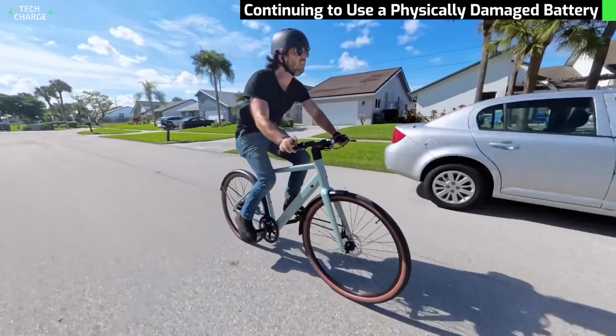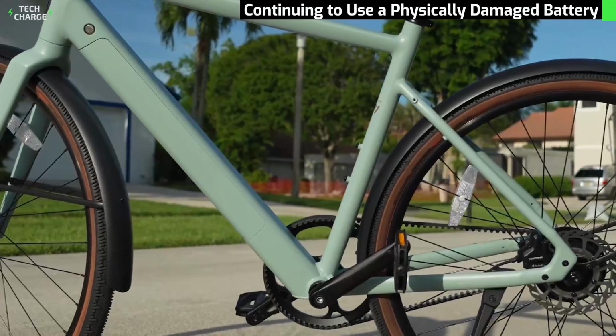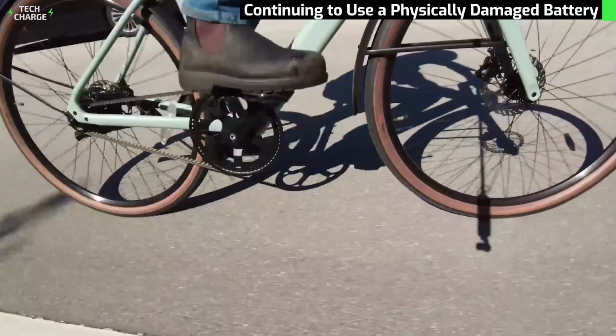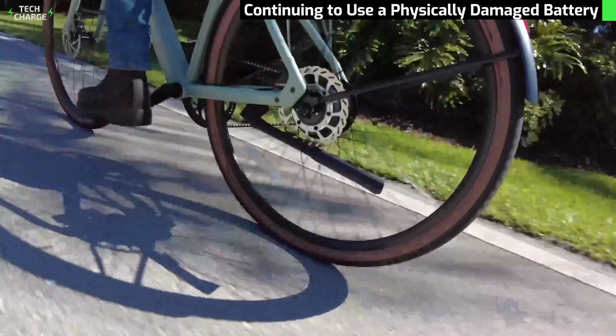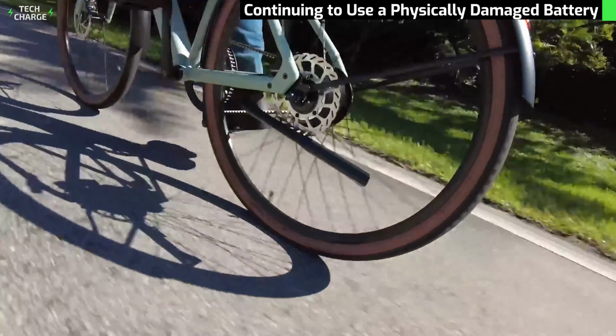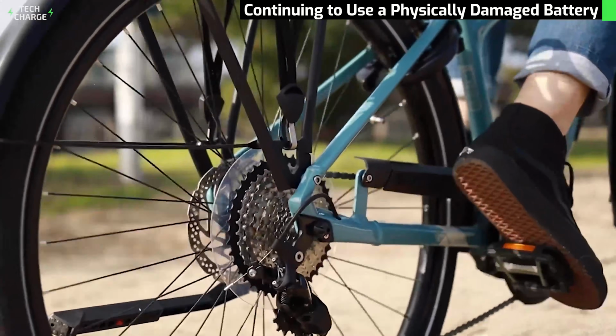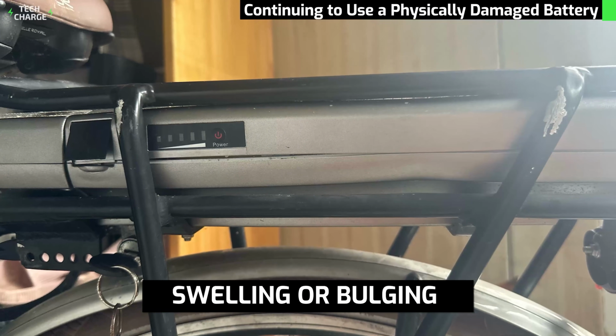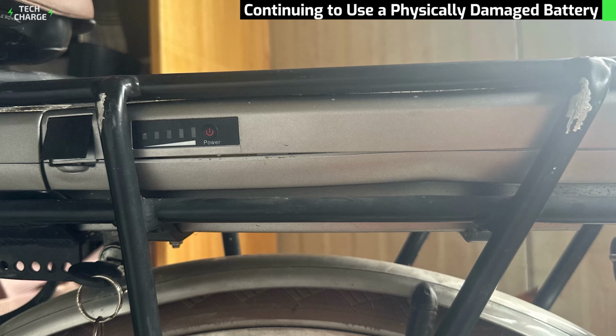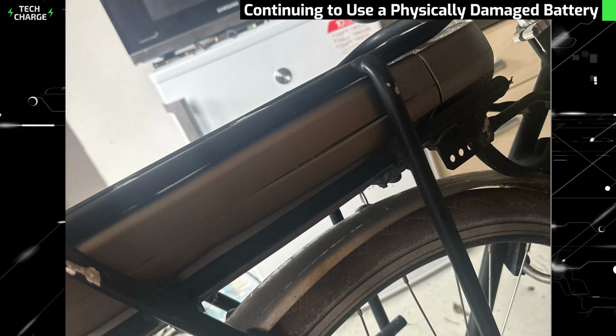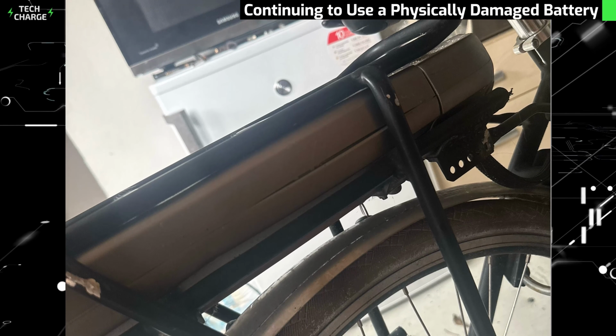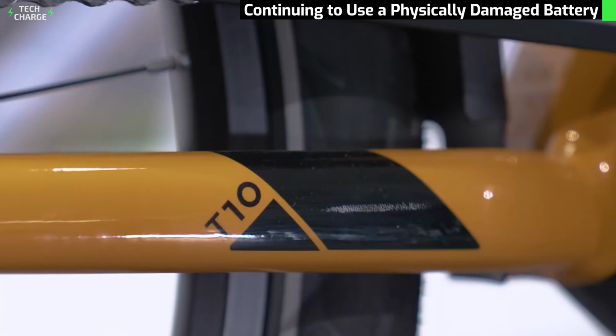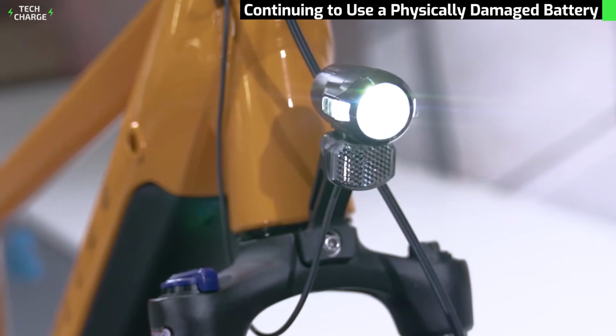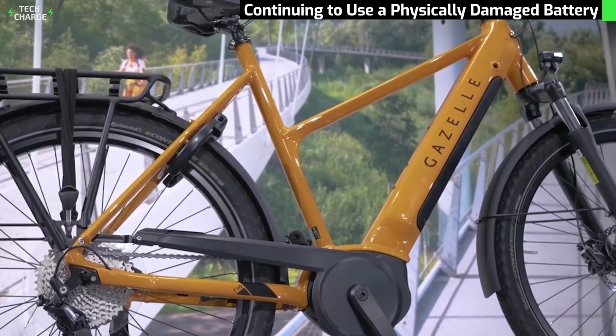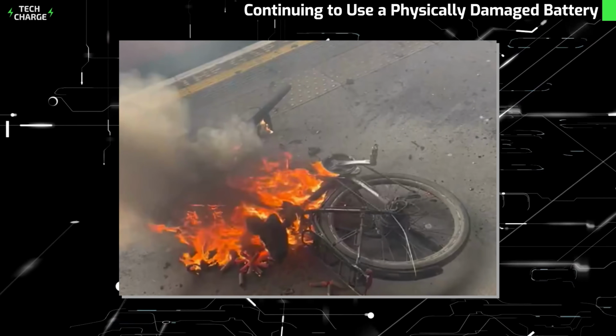External warning signs should trigger immediate removal from service. Dents in the battery case indicate the internal cells absorbed significant impact force. Punctures or cracks in the housing mean the protective shell is breached, exposing internal components to environmental contamination. Swelling or bulging of the case is perhaps the most critical warning sign because it indicates pressurized gas buildup inside the sealed container. This pressurization dramatically increases explosion risk because the battery is essentially a pressure vessel that's been compromised.